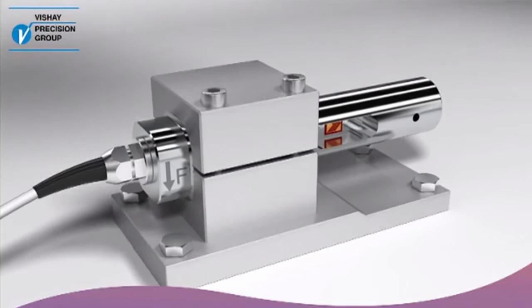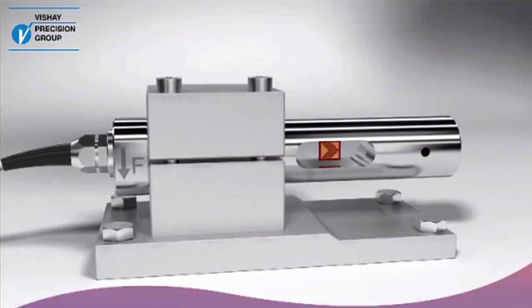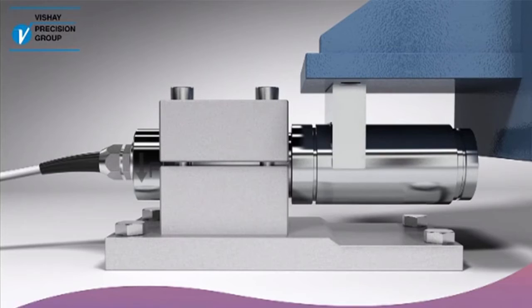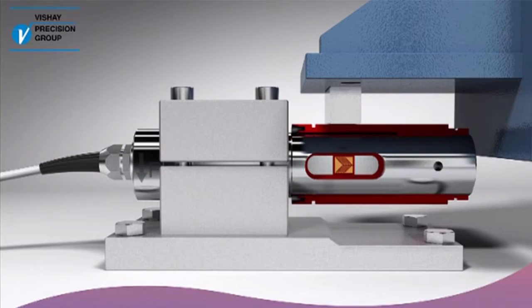The KISS load cell has a circular and symmetrical measuring element. It also has a sleeve which fits concentrically over the measuring element. This sleeve is the key to the KISS principle and was patented by BLH and Nobel weighing systems. It allows the loads to be applied in line with the strain gauges.